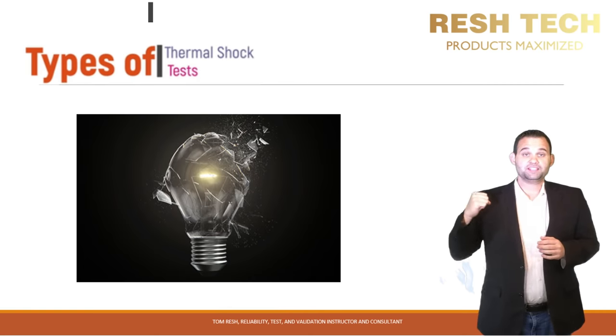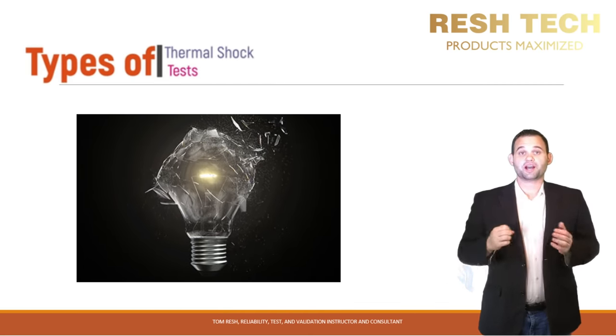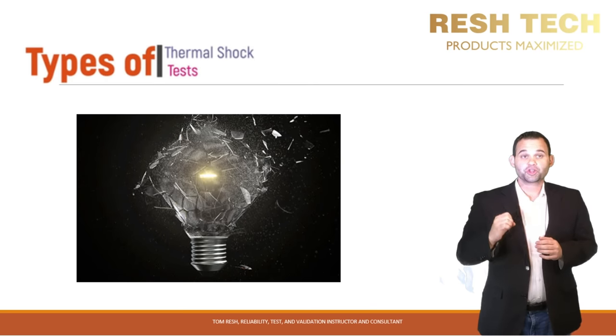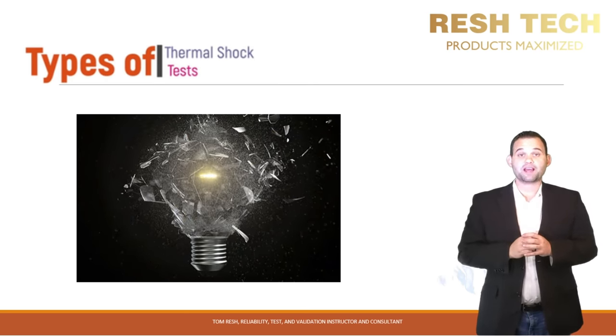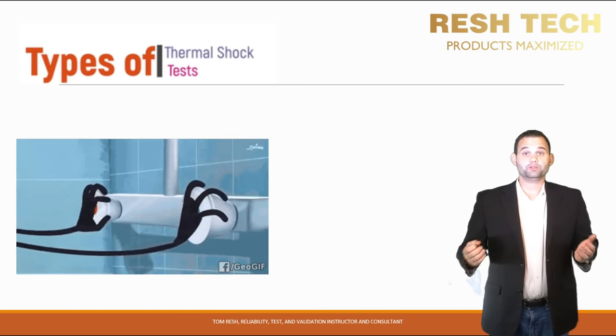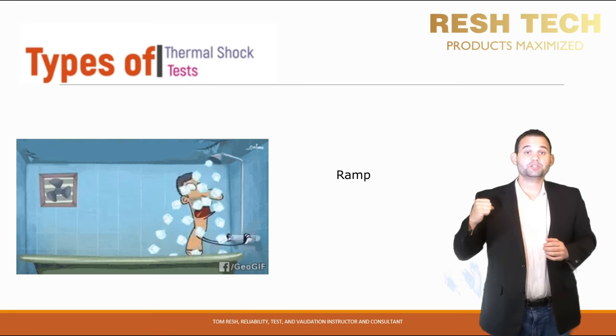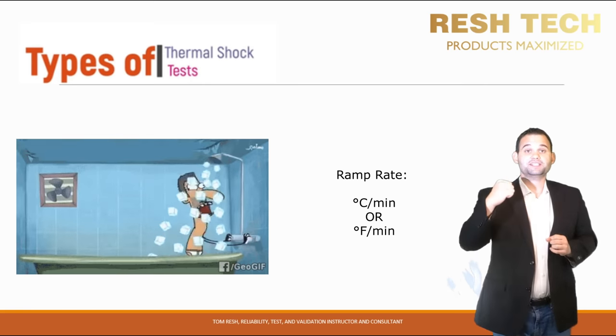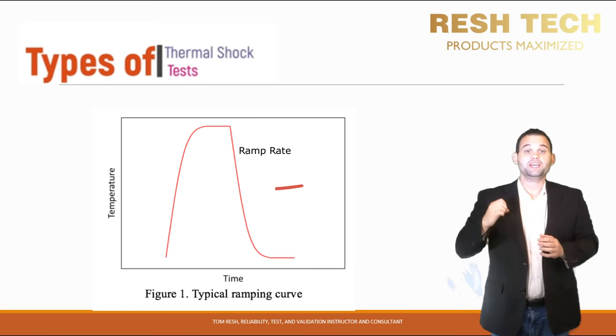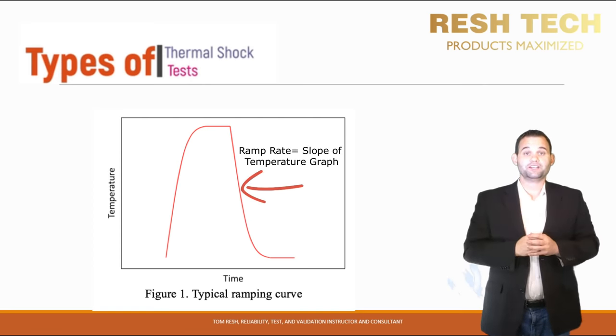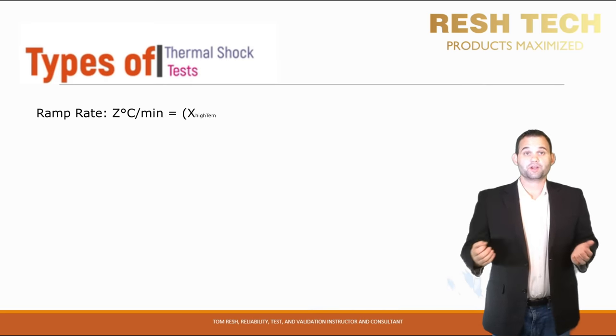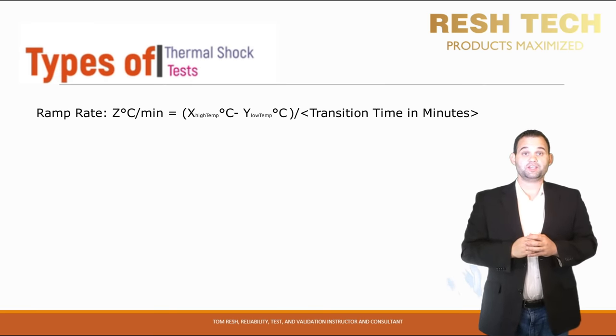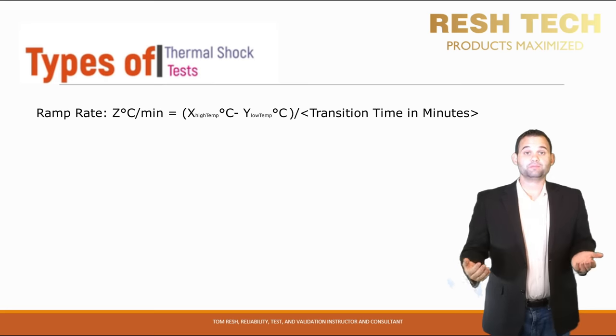This brings us to our next point: types of thermal shock tests. While thermal shock can be used to simulate real-life use cases and corner cases, thermal shock is often used to drive out defects in both the design and manufacturing process. By cycling hot and cold temperatures at a rapid ramp rate — called degrees Celsius per minute or degrees Fahrenheit per minute — you can accelerate temperature changes and drive out latent defects. Ramp rate is a simple calculation: take the delta of your temperature range and divide it by the amount of time it takes to transition between the temperatures.